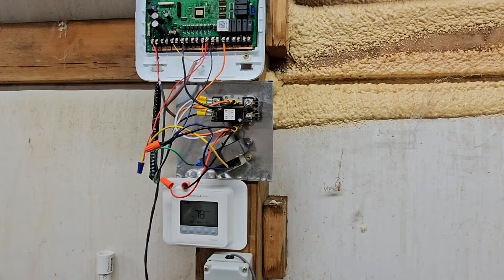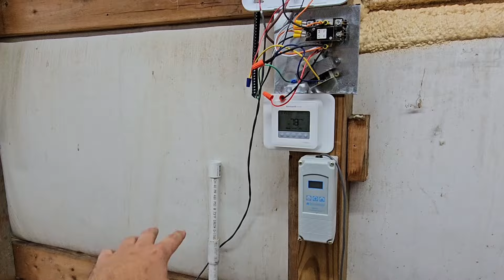And then on my indoor unit, I've just got a wire for Y, and it's tied into the coil of that contactor. So it will energize that contactor and close a set of contacts. But the contactor really does nothing. So what does something is the thermostat communicating to the AHU, and that's what turns the outdoor unit on. Wanted to explain that, but those are the 4 components. Now I'm going to show you how it works.